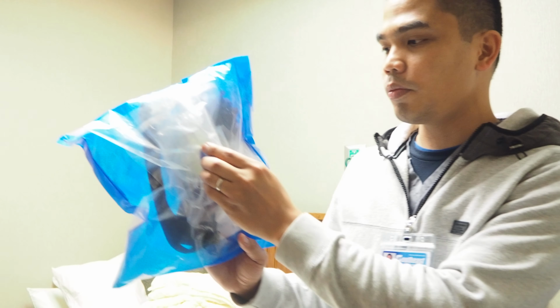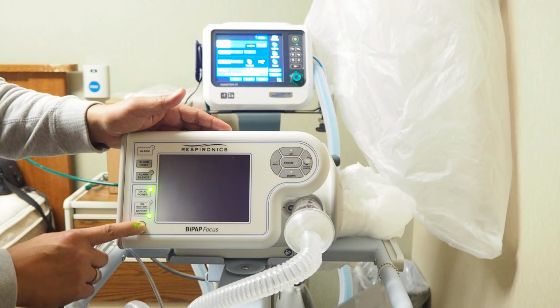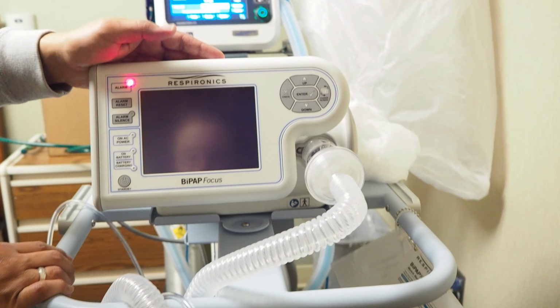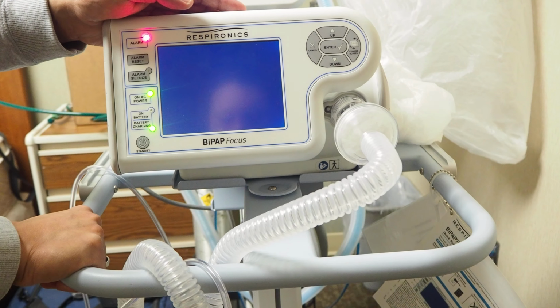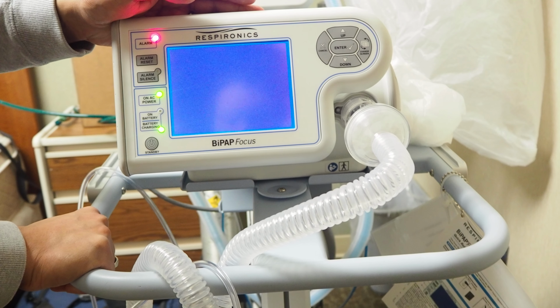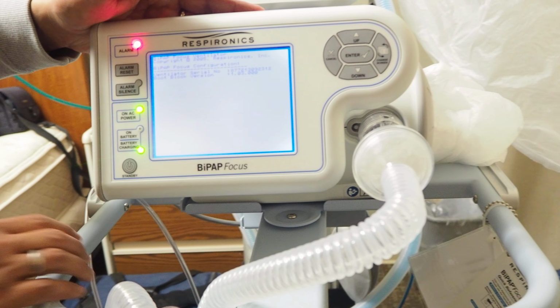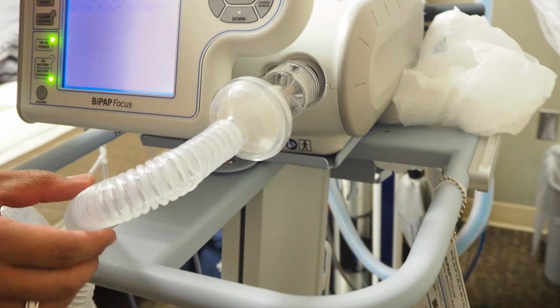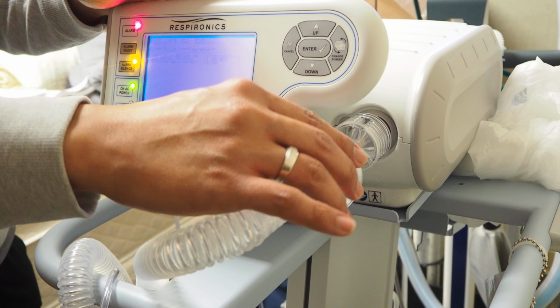So especially if we want to hook this up, assuming this one is inserted to the patient, we can immediately put this on the patient. But prior to that, we have to turn this on. So this one is a BiPAP Focus Respironics machine. We'll take a few seconds, and prior to that, we also have a clean corrugated tubing with a bacterial filter. It should be inserted tightly.